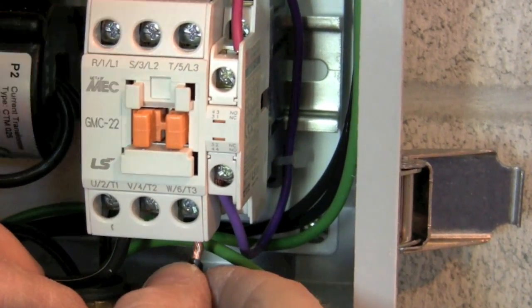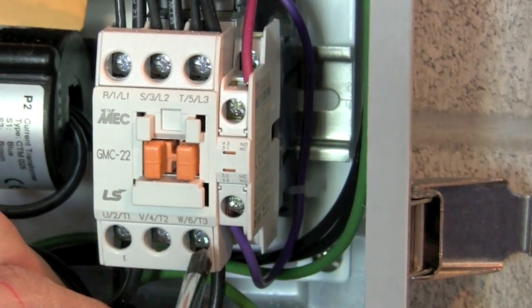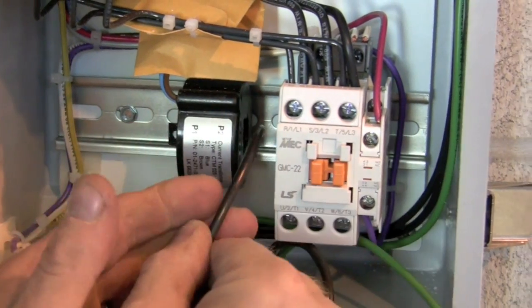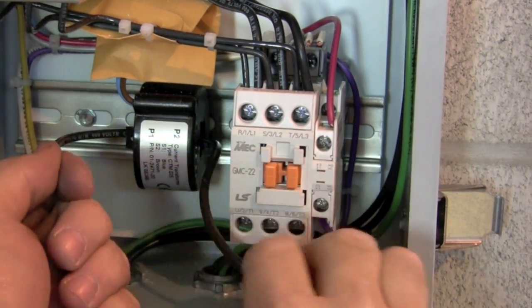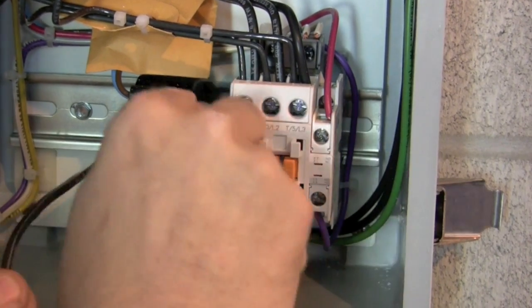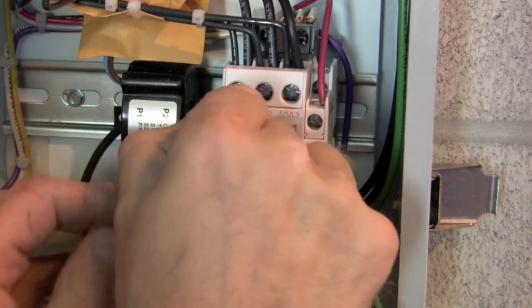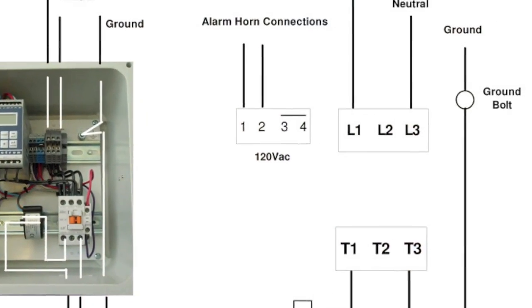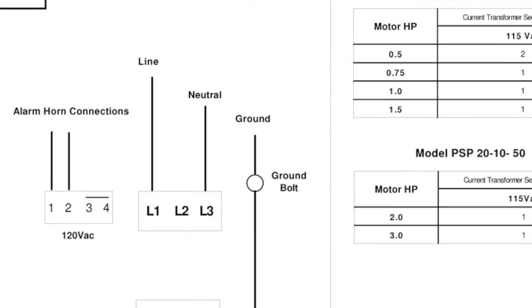Terminate the existing T2 wire going to the pump to the T3 terminal on the bottom of the PSP20's contactor. Terminate a 12 inch length of appropriately sized wire to the T1 terminal on the bottom of the contactor. Take the other end of this wire and pass it through the center of the current transformer. The number of passes of wire through the center is determined by the full load amps of the motor and the associated chart in the manual.